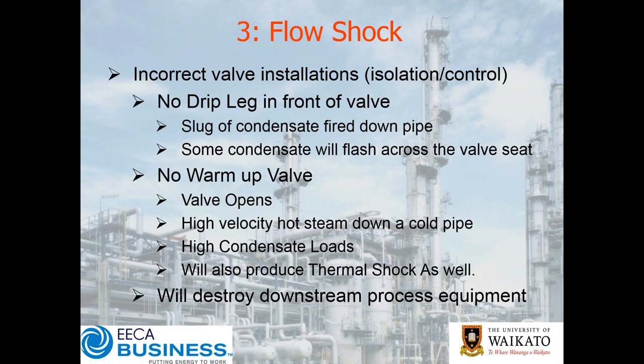Now we'll go on to the third cause of water hammer: flow shock. Flow shock is really about incorrect valve installation — it could be isolation or control. What happens is if you have a control valve or any valve, you should have a drip leg in front of that valve. The purpose of that drip leg is that any condensate going along the pipe should be dropping into that drip leg instead of going through to the valve, so we should have dry steam hitting our valve.